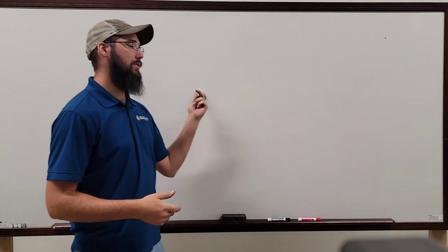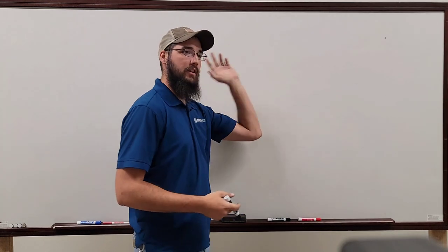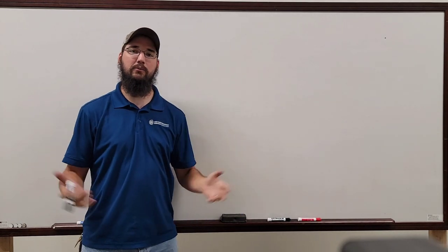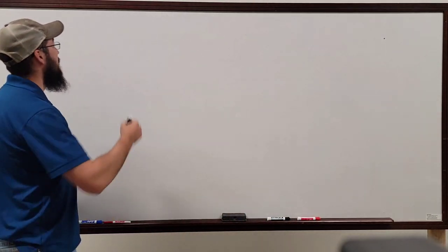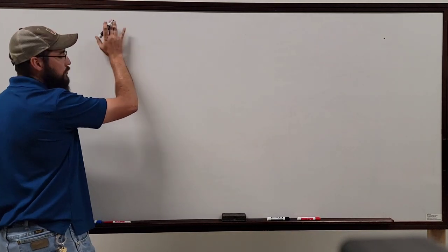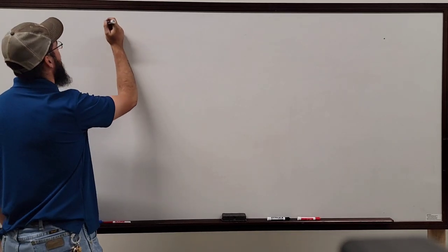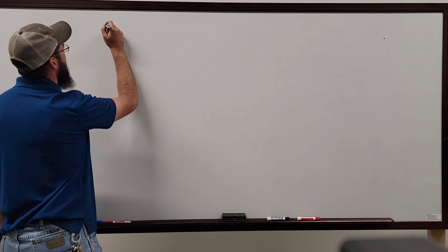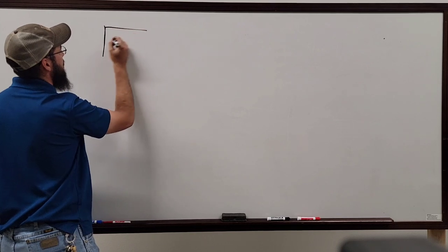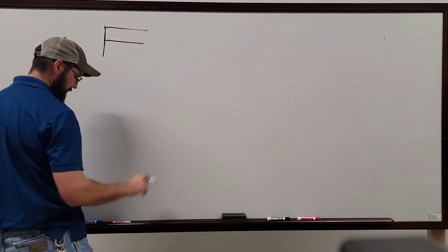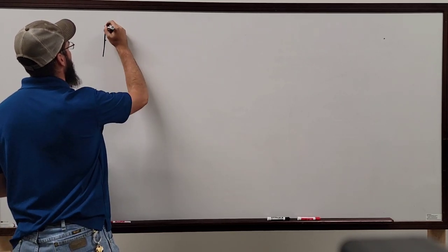All right, so single phase heat, we're pretty familiar with, right? You've got two lines in, two lines out, everything connects. It either works or it doesn't, right? Okay, three phase is where people get in trouble. So there's two styles of three phase wiring schematics. The first one I can draw from memory without too much trouble. So you will have a common bar, and off of that bar, you will have your independent heaters, with little squiggly lines.